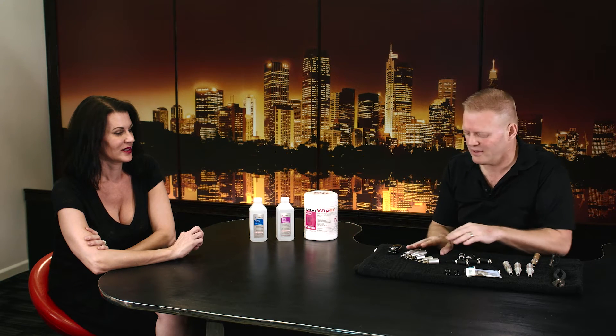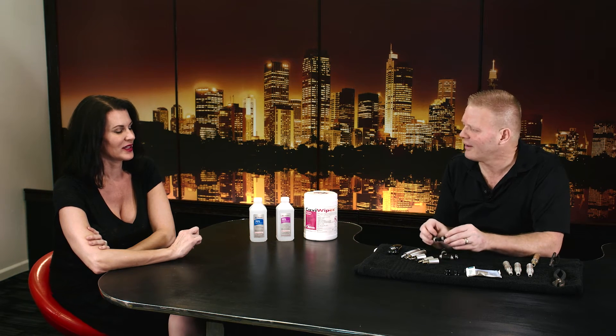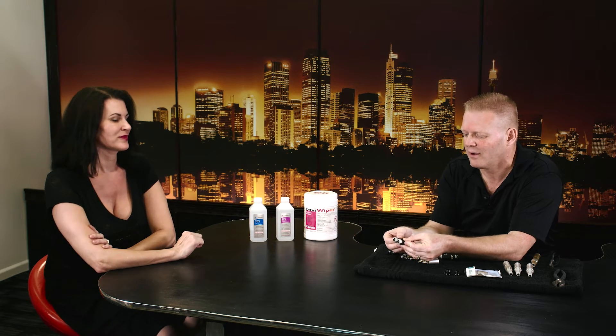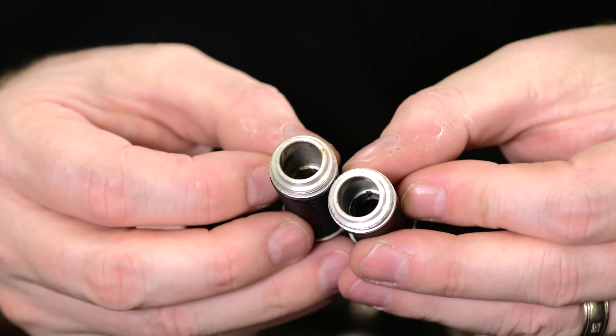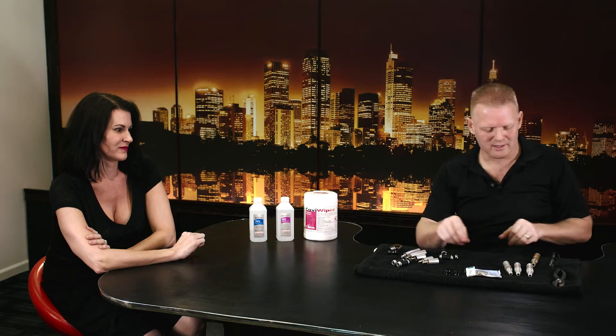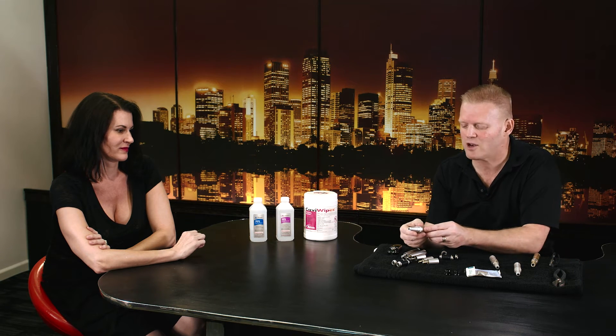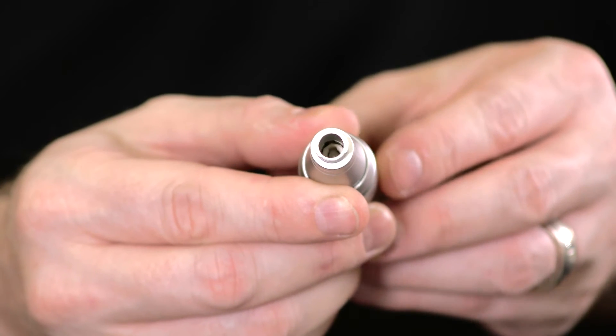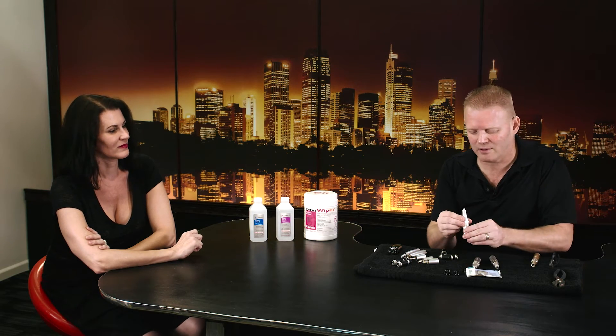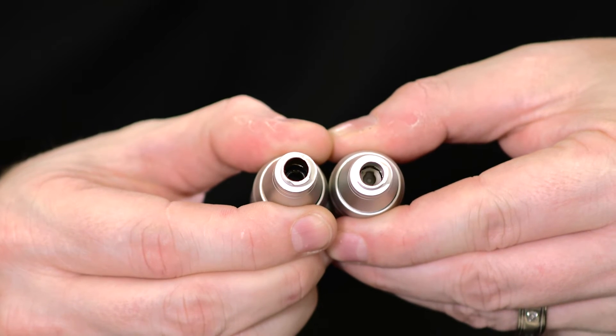So what is this stuff? Isn't it just lubrication? No — it's blood and products. How did it get in there? It leaked through the cartridge and got right into the pen. You might say it's just the design of this particular cartridge and pen system. But there's another device out there claimed to be better because it has a safety cartridge with a silicone membrane that nothing leaks through. Here's a brand new one — do you see anything in there? It's brand new, so it looks silver and clean. Let's look at a used one. You can see from the side that the used one is dark on the inside.